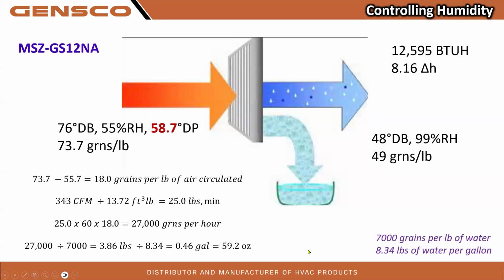So how does mechanical cooling work? This is an example of, say, a house at 76 degrees, 55% relative humidity. The dew point is 58.7. All we need is our coil to be below that to begin to condense. And if we can get a really cold coil, 40 to 45 degrees, we're going to condense faster. Now, within that air, the absolute humidity is 73.7 grains per pound of air. And to put that in perspective, there are 7,000 grains per pound of water. We need 7,000 grains to equal 1 pound.